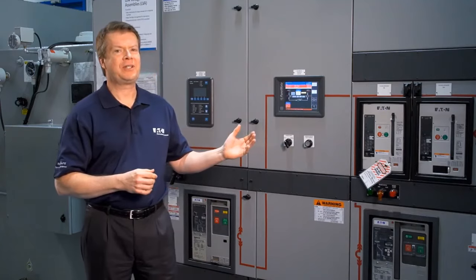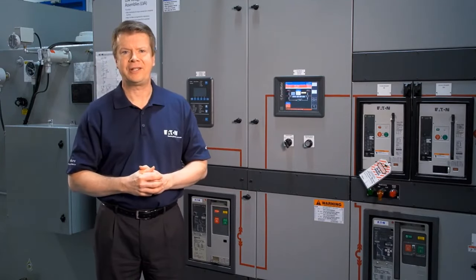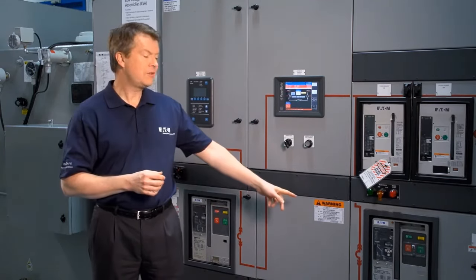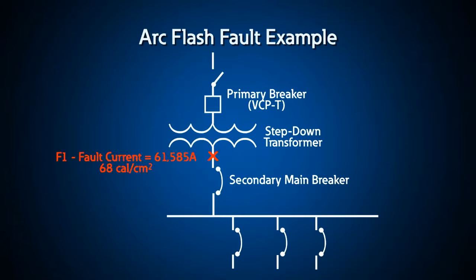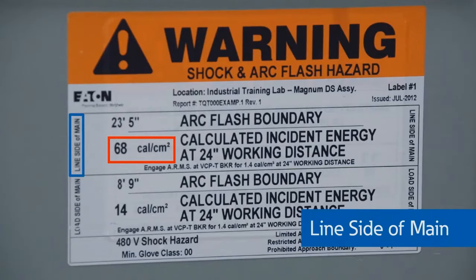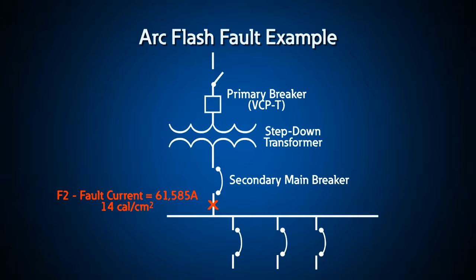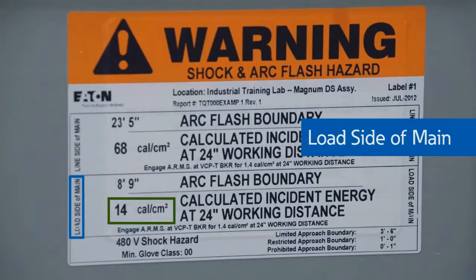This low voltage assembly illustrates a very common yet very dangerous situation. The arc flash label indicates that the arc flash energy on the primary side of this breaker is 68 calories, well above the maximum allowed when wearing a 40-calorie suit. Yet on the secondary side of the breaker, it is only 14 calories.